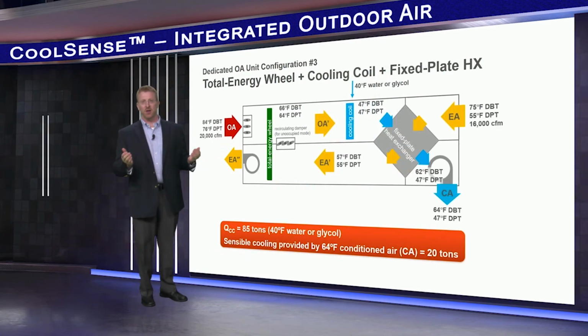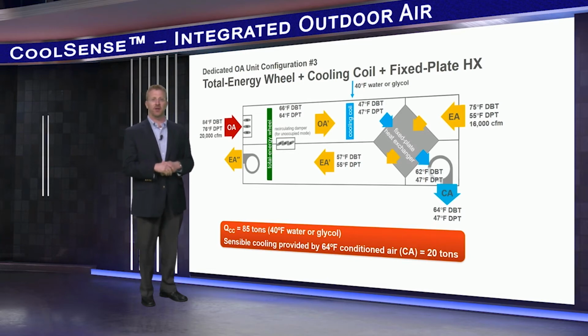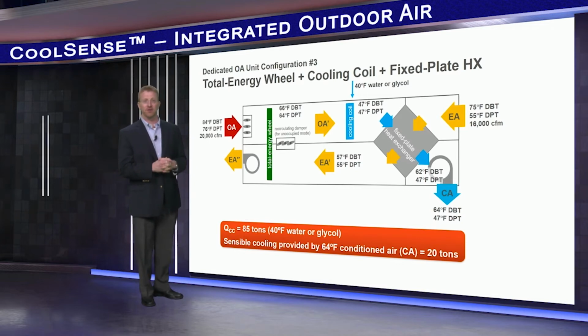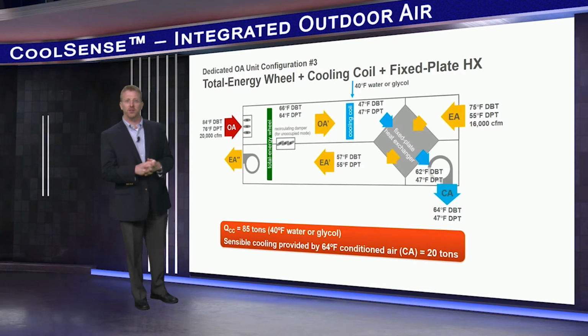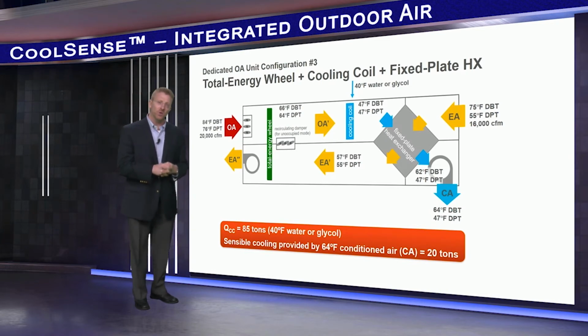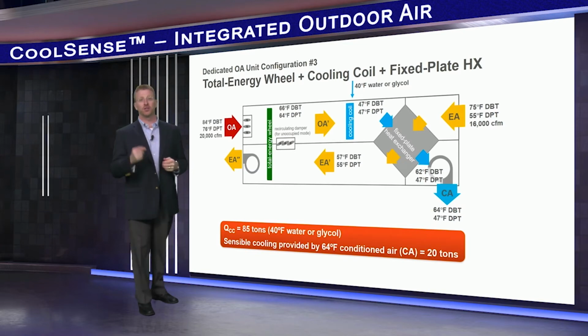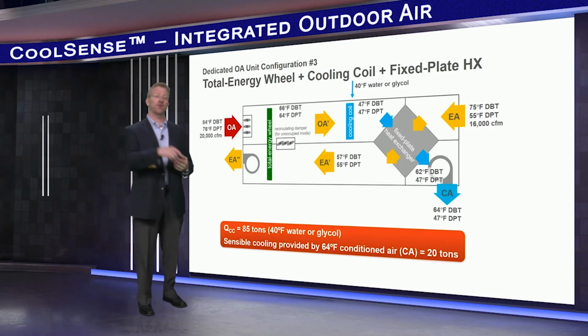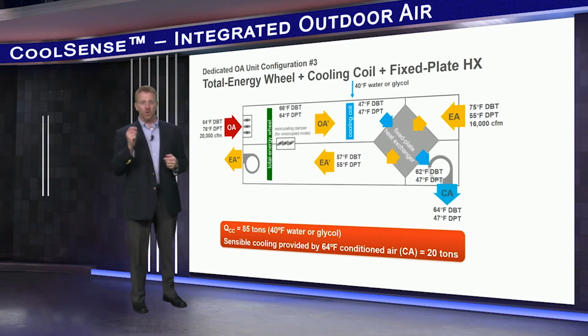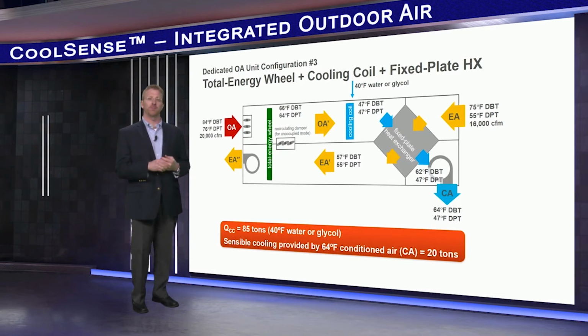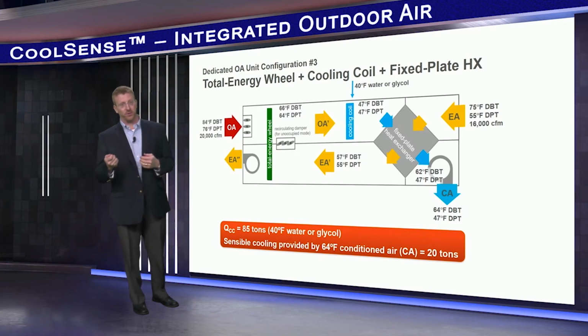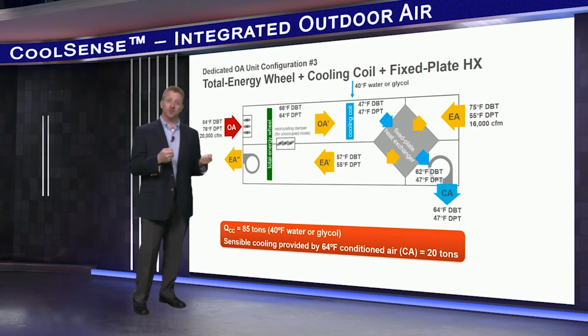No CDQ wheel here, but now we have included a fixed plate sensible heat exchanger located downstream of the cooling coil. This device transfers sensible heat from the warm exhaust air to reheat the cold dehumidified air. This configuration provides the unique benefit that the heat exchanger pre-cools the exhaust air, allowing the total energy wheel to pre-cool the incoming outdoor air even further. Note we're still delivering the same required 47-degree dew point, but this time at 64-degree dry bulb. This shifts even more load from the dedicated outdoor air unit to the terminal units. So this results in the smallest capacity cooling coil, only 85 tons.